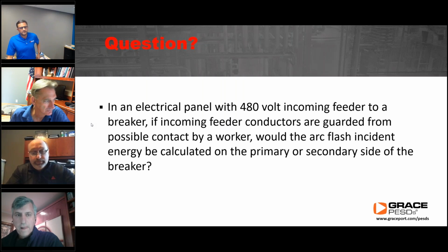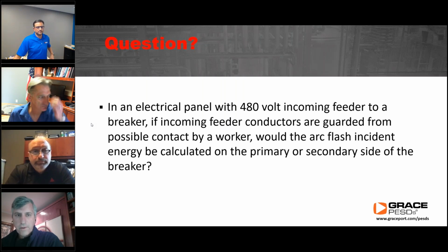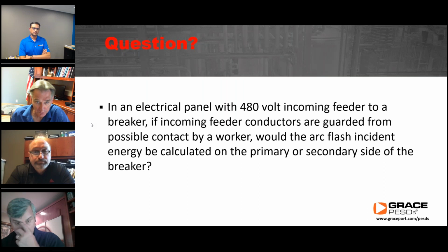From an arc flash standpoint, a pad mount transformer has this ability: if you open the right side, the left side, the high voltage side, is bolted shut with a steel door rated the same as the door you're opening. If you have effective isolation, you can assume the other part of the system won't become involved. In truth, we've done forensic investigations where we melted steel — the arc lasted long enough to burn a hole in the enclosure and still had enough residual energy to kill somebody on the other side.